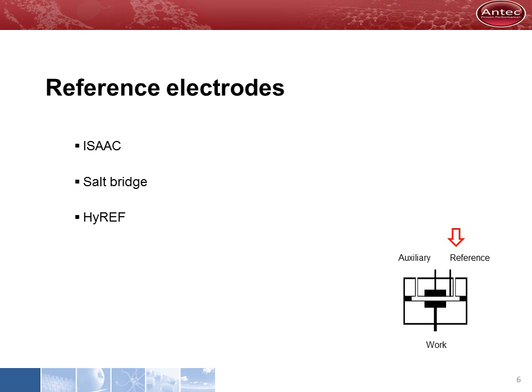Different reference electrodes are available for different applications. The ISAAC and the HyREF are in-situ electrodes in direct contact with the mobile phase. The salt bridge has a closed chamber with dissolved potassium chloride salt. The choice for a reference electrode is based on the mobile phase conditions.